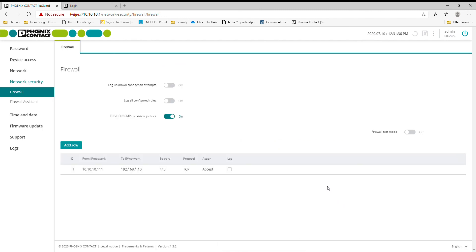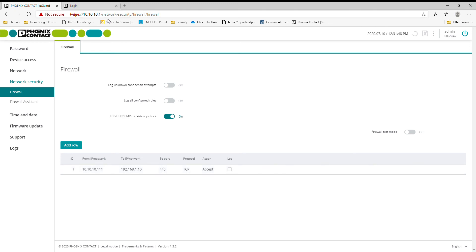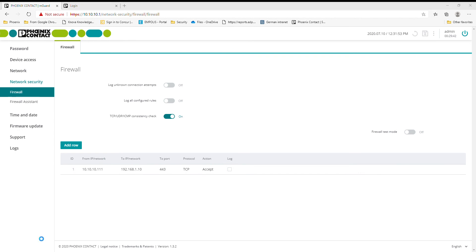I hit stop. I'm just gonna say yeah, it's gonna be moved. So now it's stopped, and you can see here this 111, which was my PC going to the PLC 192.168.1.10 on port 443 - this is HTTPS - is allowed. So that now works. If I were to open up another utility like PowerShell or the command prompt or whatever and try to ping this unit, it will fail.